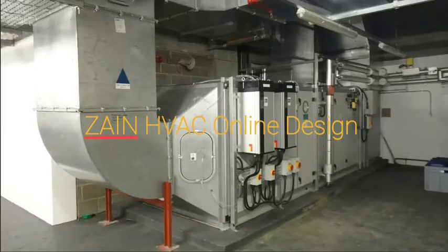And the fan is obviously pushing that, so if you change the speed of the induction motor, if you change the frequency that it's operating at, from 50 or 60 hertz down to 40 hertz maybe, then you'll slow the revolutions of the induction motor down, and that's directly connected to the fan, or maybe not directly coupled. It might be on a belt drive, etc. But you can change the flow volume of air into the space through these here.